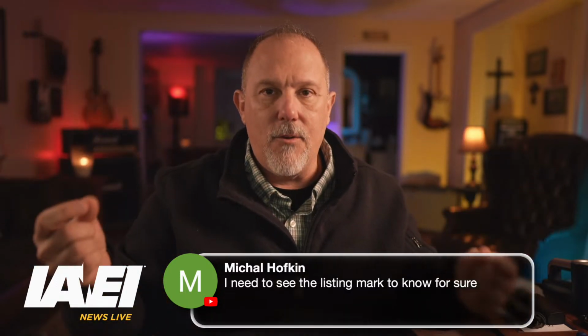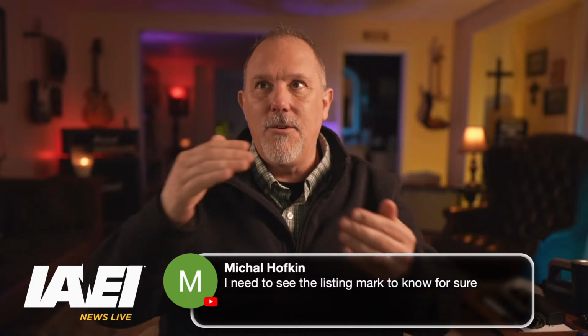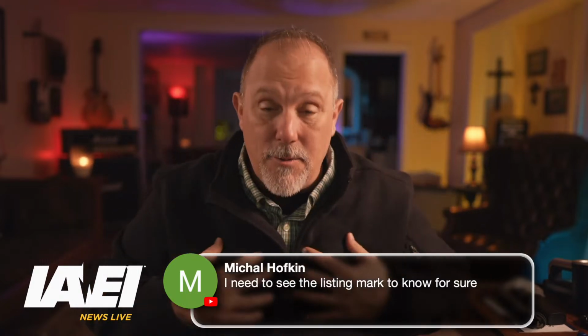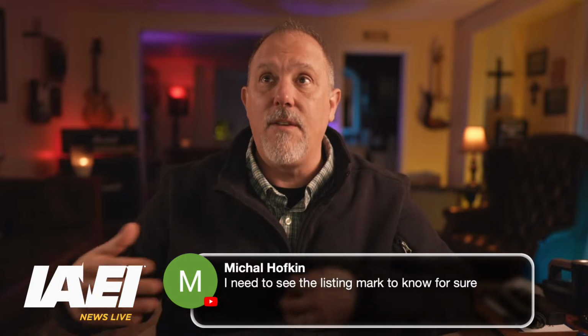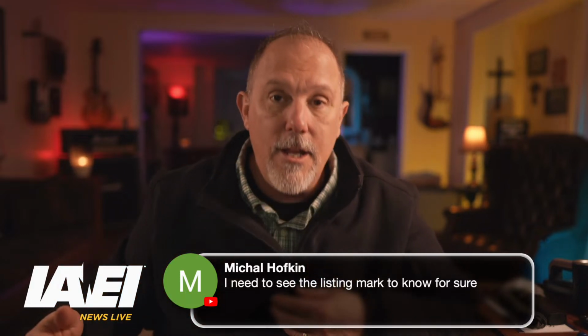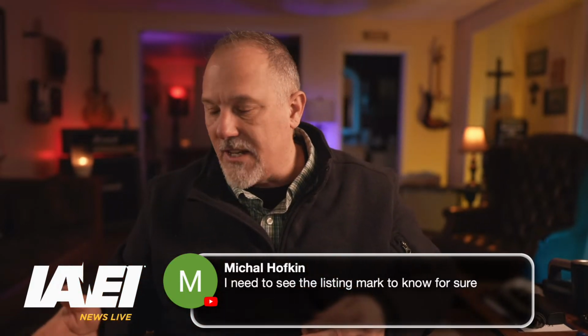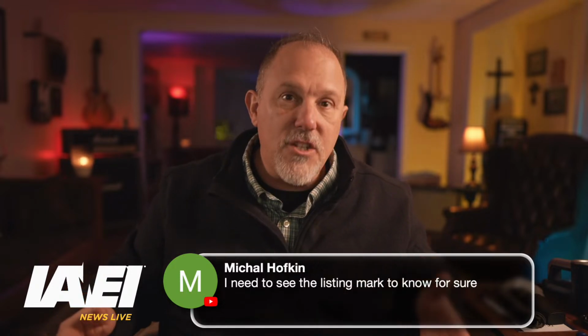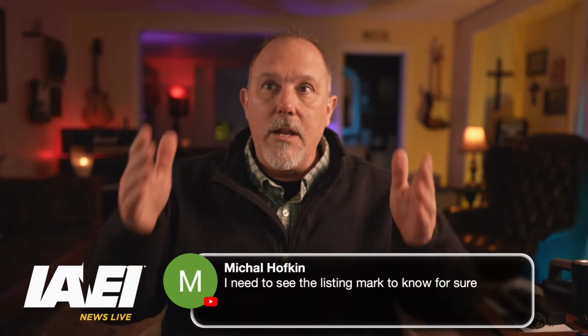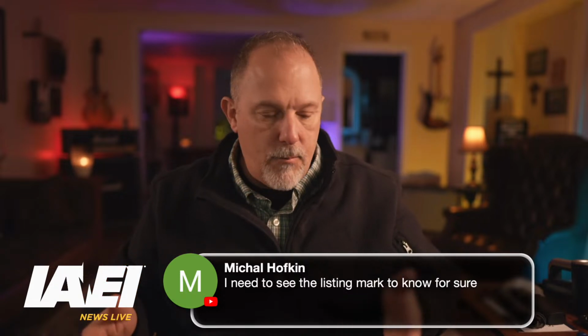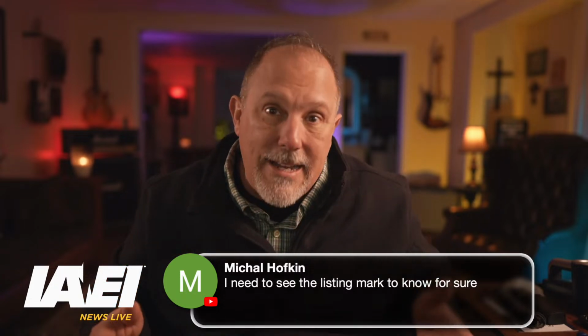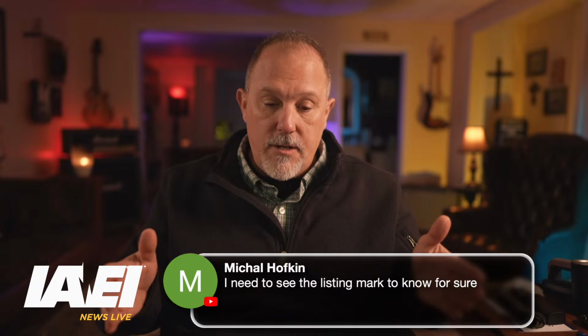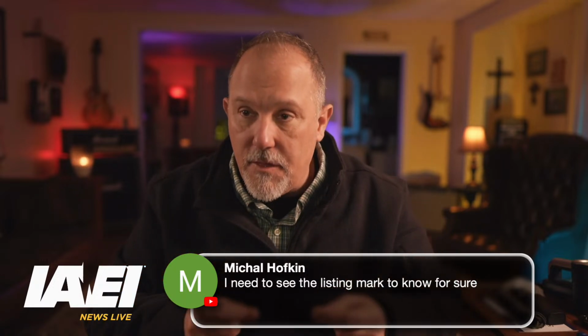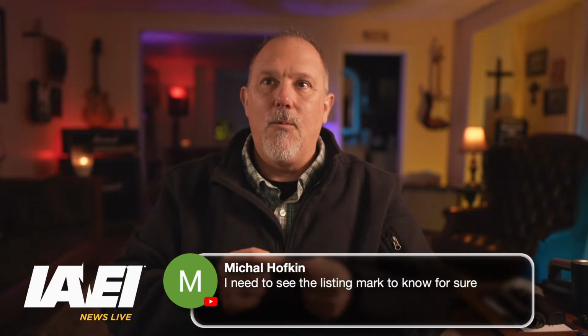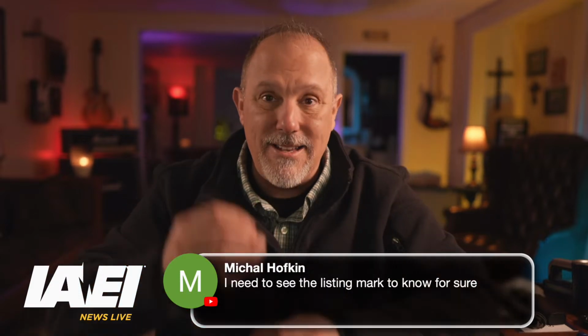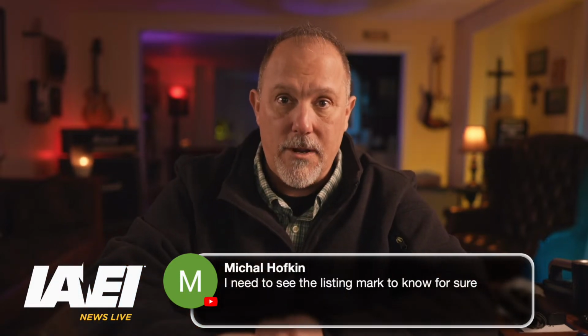We have to figure out what that is. I would have thought it was in Chapter 3, but we find out it's in Chapter 4, and we have to determine if it's a flexible cord or cable, or a fixture wire. Then we looked at 400.4 and 402.3, and determined the conductor we're dealing with. Then we say, okay, what is that application? Then we look at the listing requirement for the product itself.